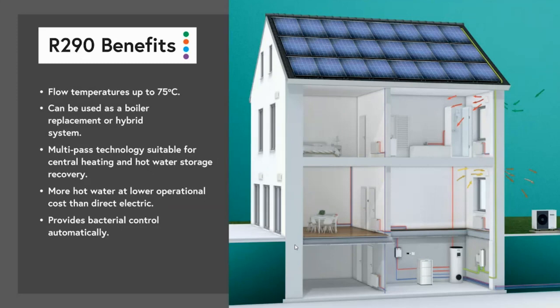A lot of people ask, well, how much does it save? Well, it's a little hard to answer that because it varies all the time, because the heat pump's performance is obviously tied to the outside air temperature. So in cold climates, the efficiency is lower. In warmer climates, it's much higher. But on average in New Zealand, you would expect to get about 2.5 to 1, or a COP of 2.5, or 250% efficiency. And what that means is that you're effectively reducing your electrical load by about 60%. So that's the expectation of a good high temperature heat pump for hot water production.